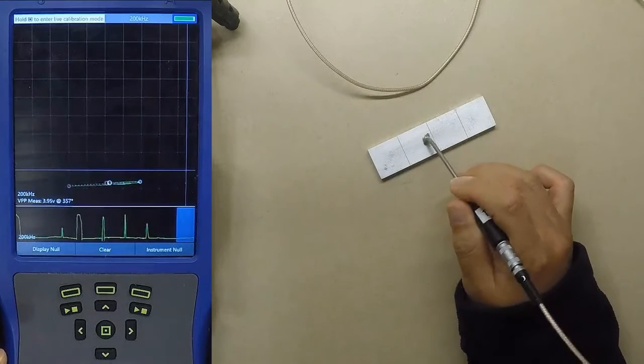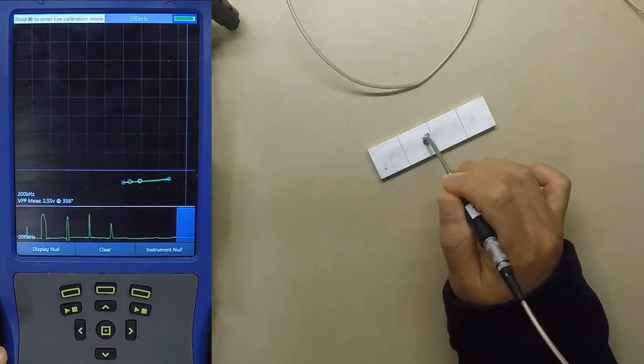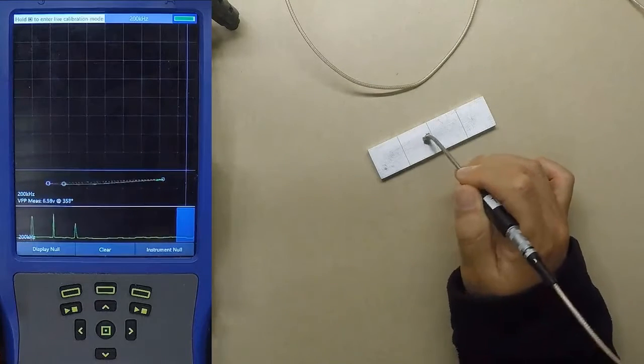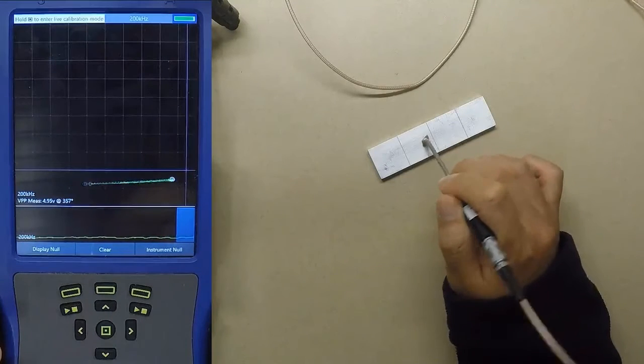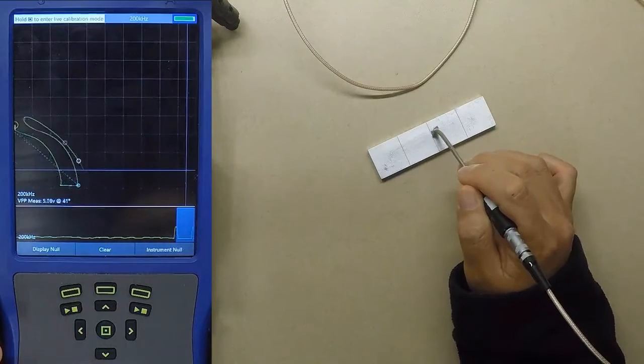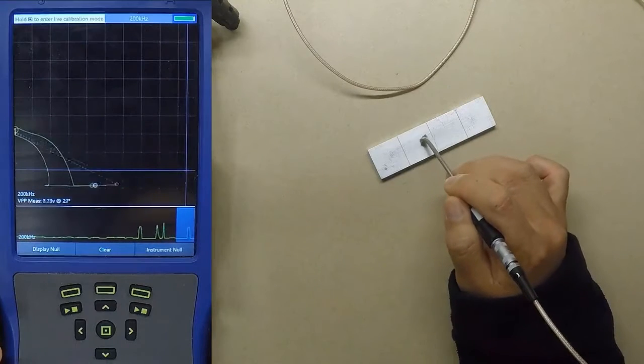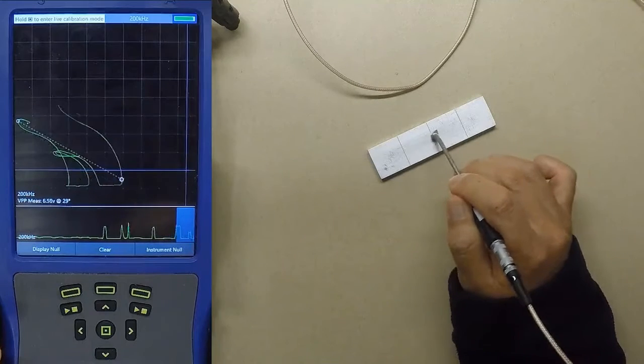As you can see, any amount of liftoff really can move the operating point on the screen. You can see here where these EDM notches form on the screen depending on the liftoff of the probe. You can see that there is significant drift.